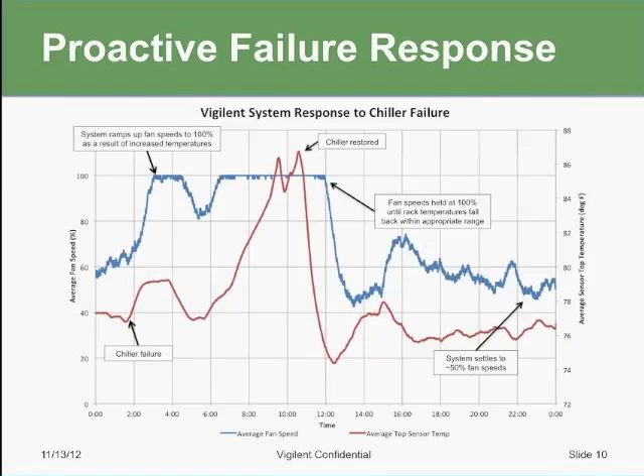So what does an operational redundancy system look like? Well, this is an example over the course of a day of a downtime incident where a chiller had failed in a data center. And a cooling control system was installed in this facility, and it had responded appropriately. So what you're looking at here is on the x-axis, 1 day from midnight to midnight. And on the left y-axis is the average fan speed, which is indicated by the blue line. This was a CRAH deployment where the Vigilent system was controlling VFDs.